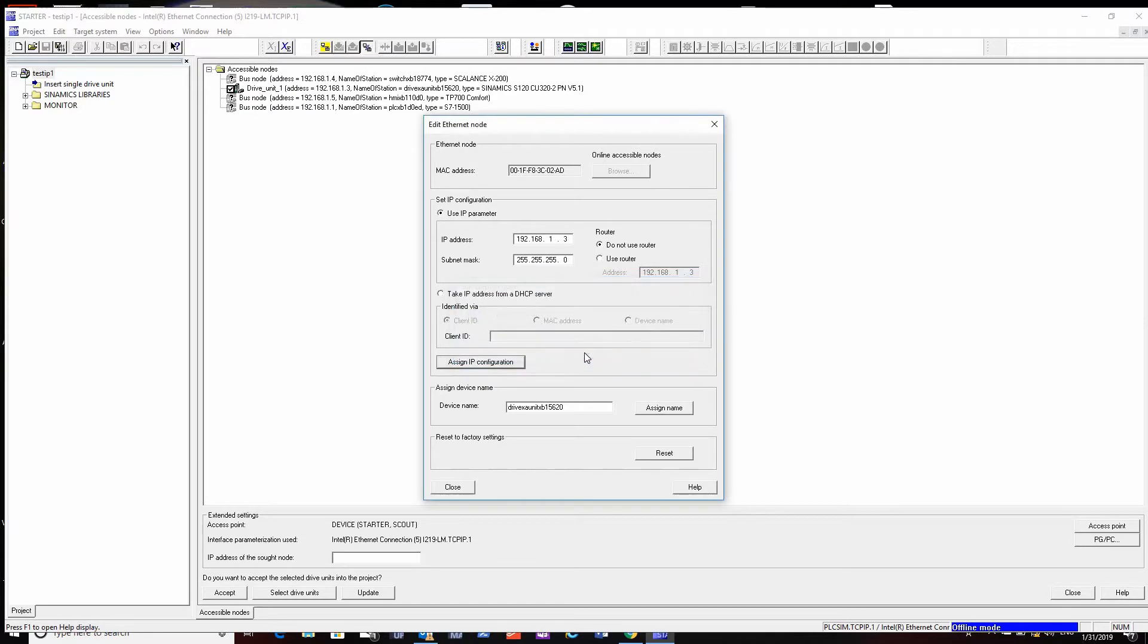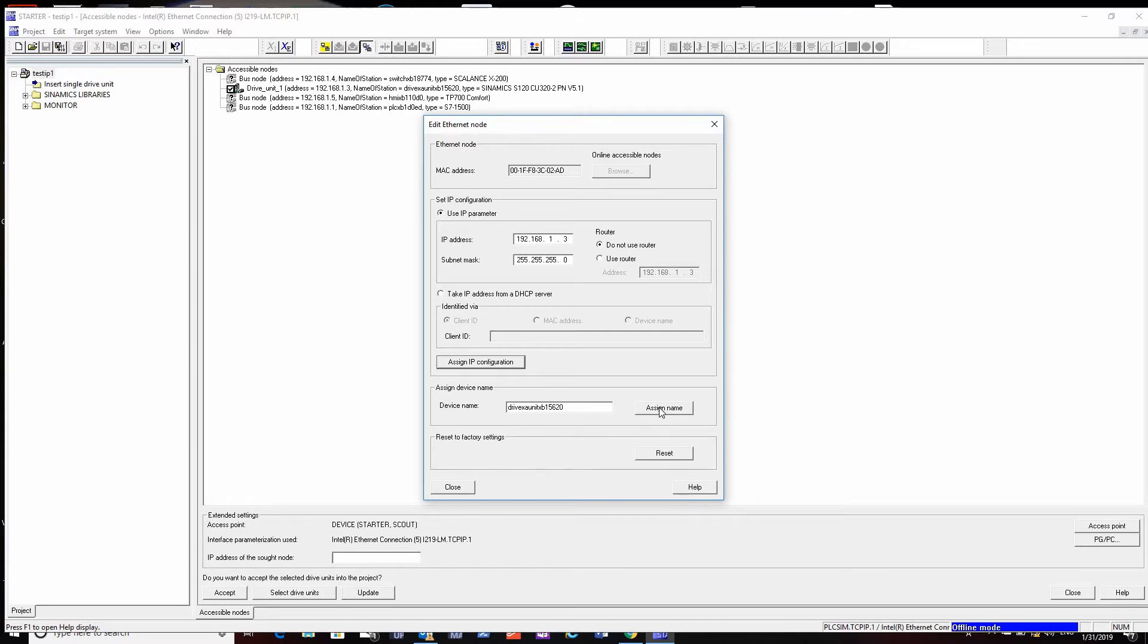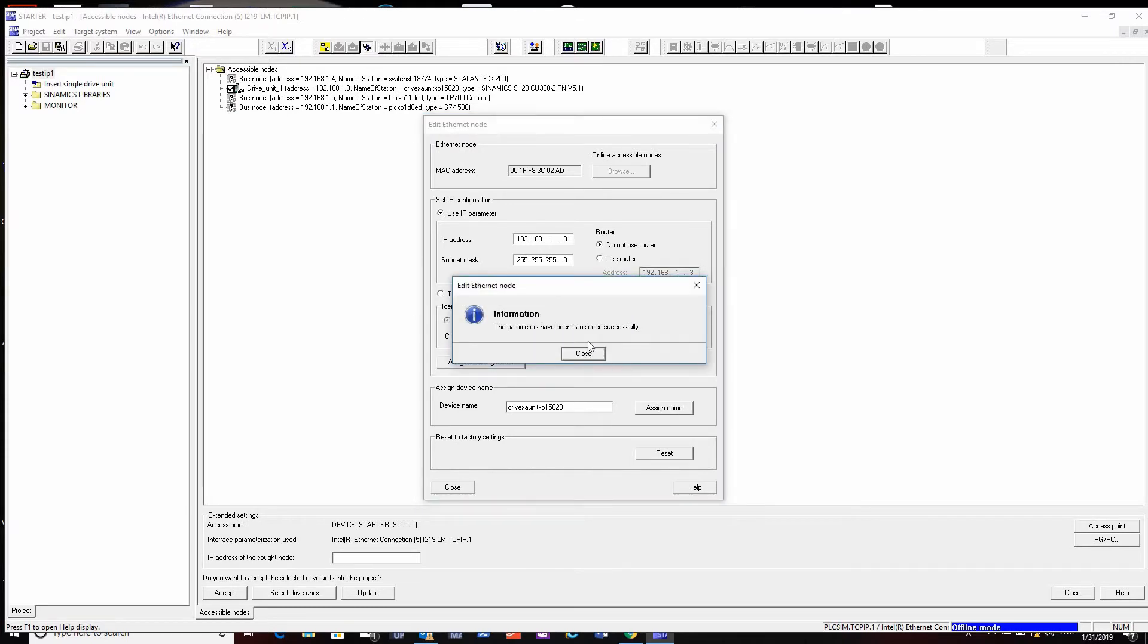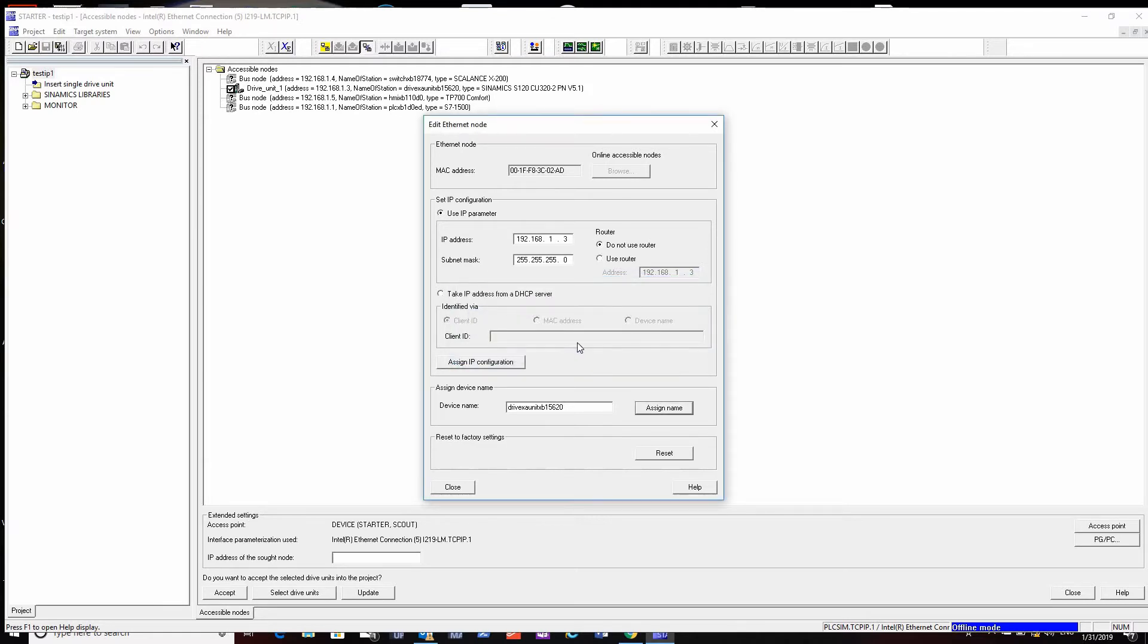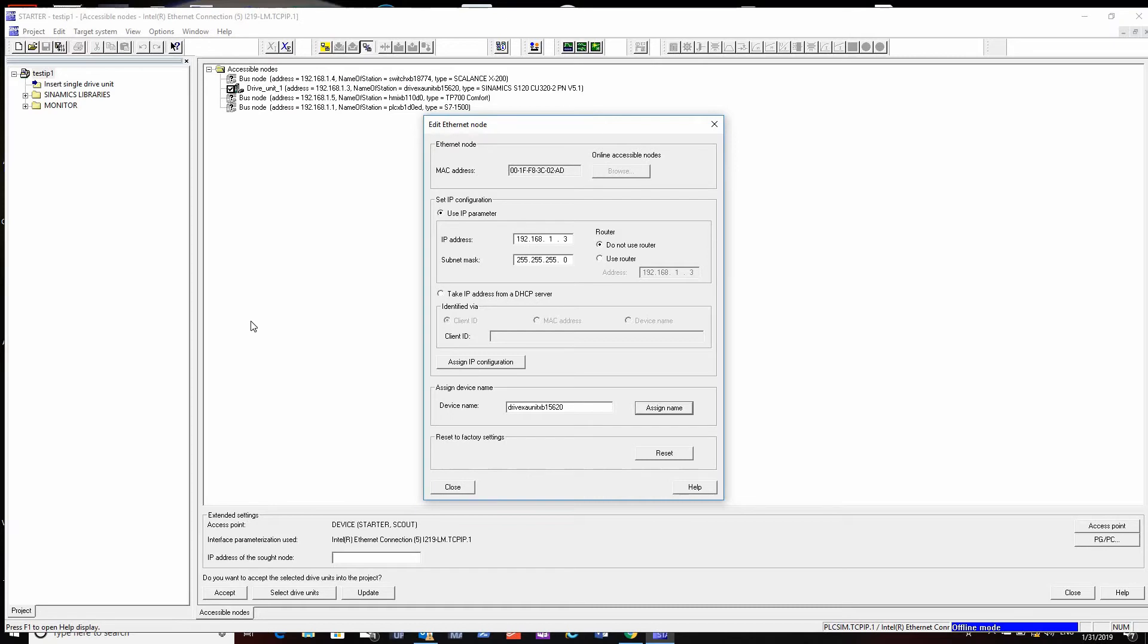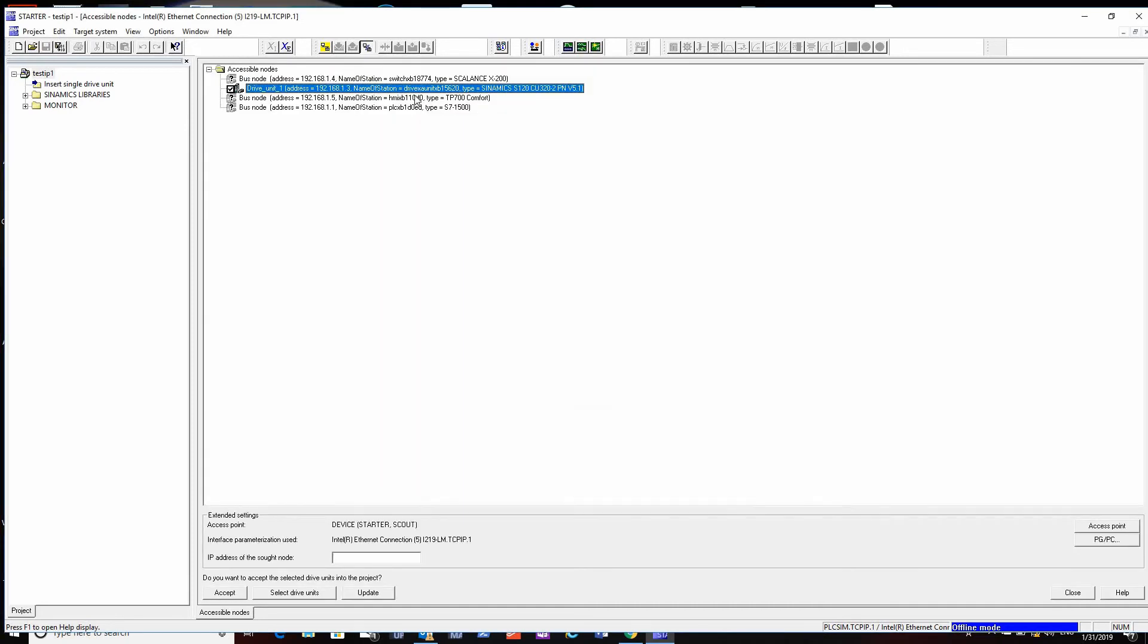Then it will set the address as long as the drive is not running or talking to a PLC already. If it is, you'll get an error - it won't let you change the IP while it's running or another processor is controlling it. You set the appropriate name and that's all you have to do. It writes right to the Ethernet chip inside the drive, the Profinet chip, and your address is set. You don't have to do anything else.